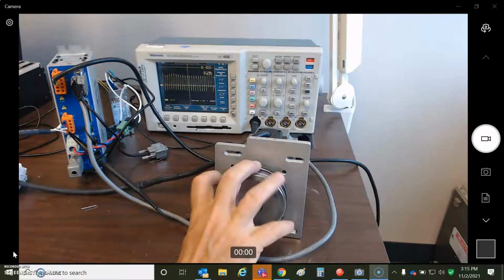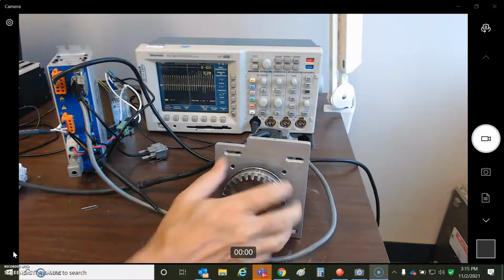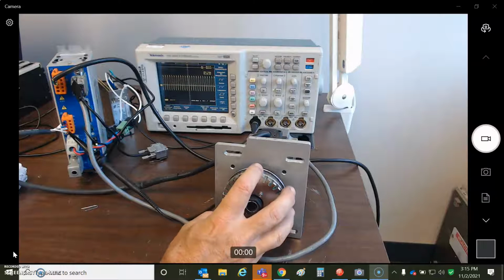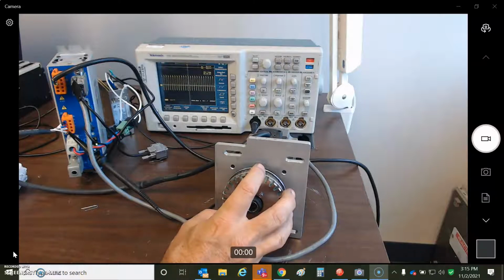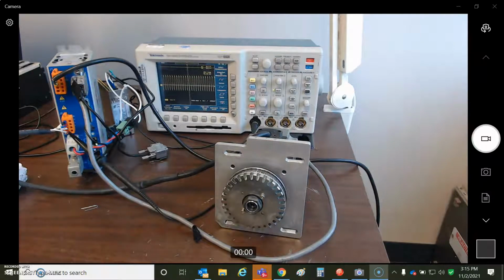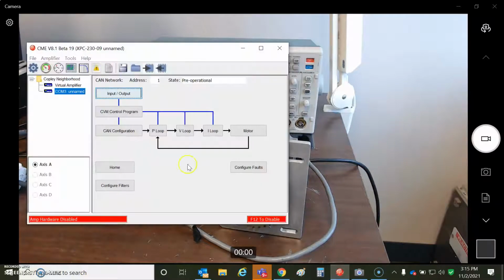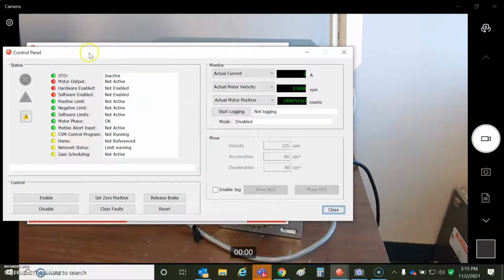Oh, that's not how dynamic brake works. While the drive is disabled, at the time of disable, if there's a voltage, it'll stop it and control the current. But after the current gets to zero, then the output stage becomes disabled again. So it's a little bit of an unusual dynamic brake, but it serves the function of stopping. So we'll take a look at how this works.